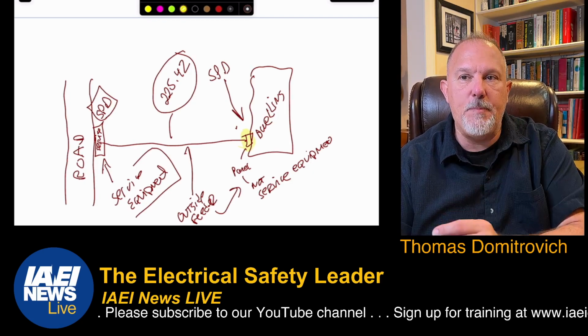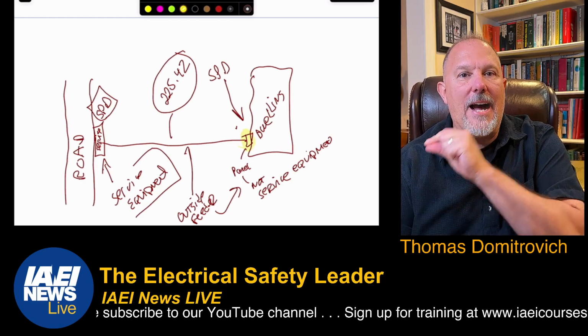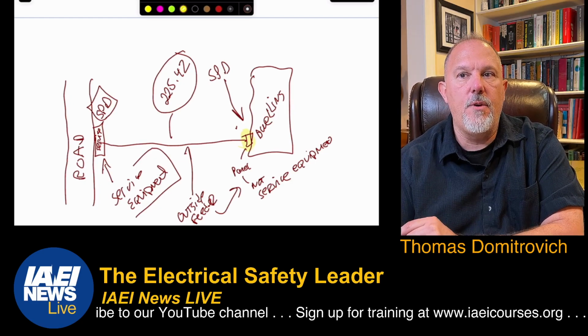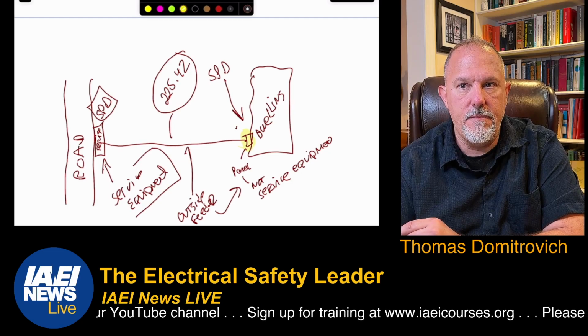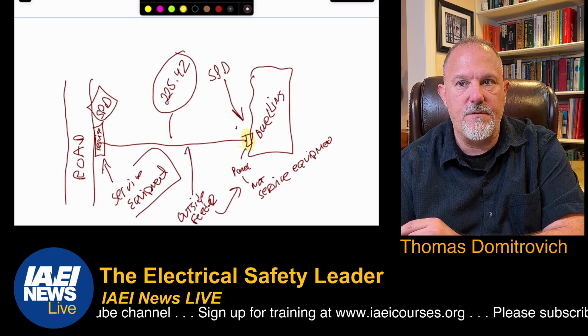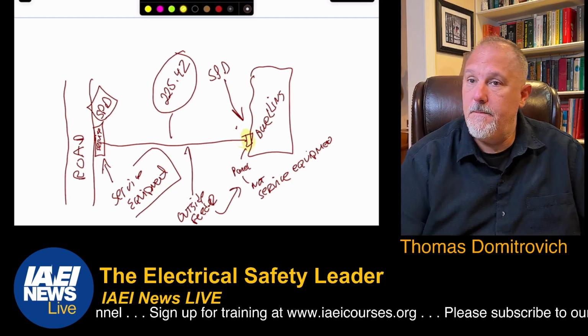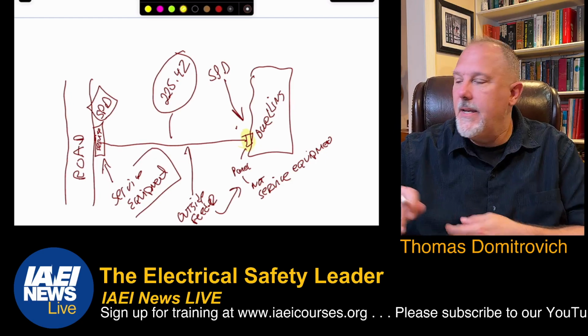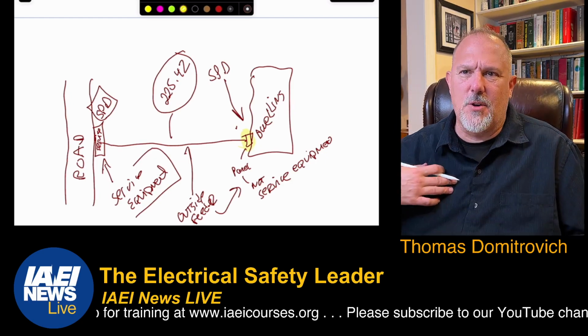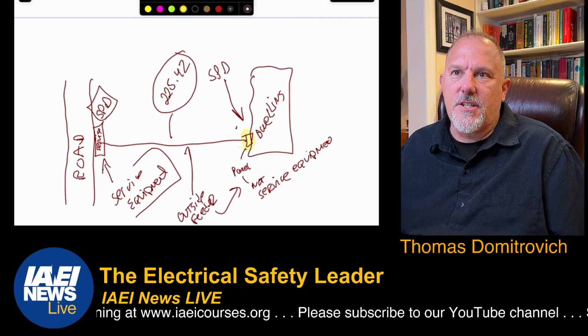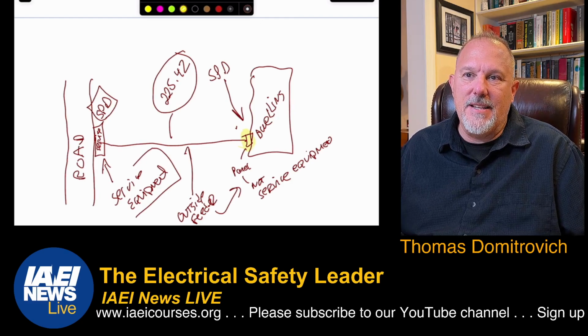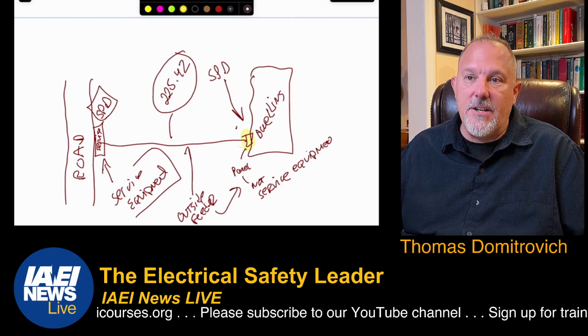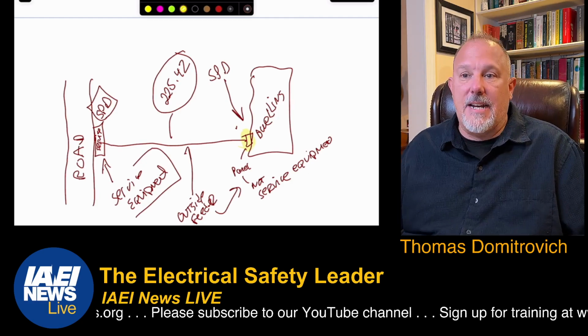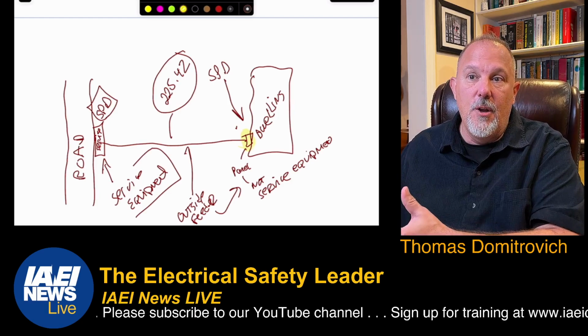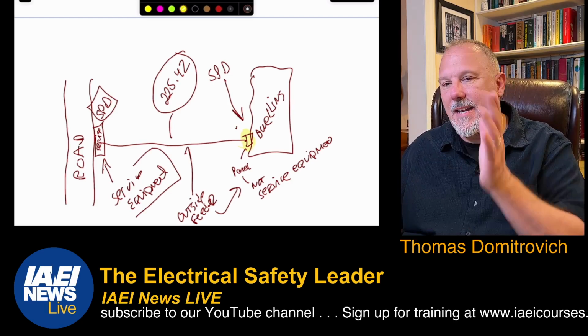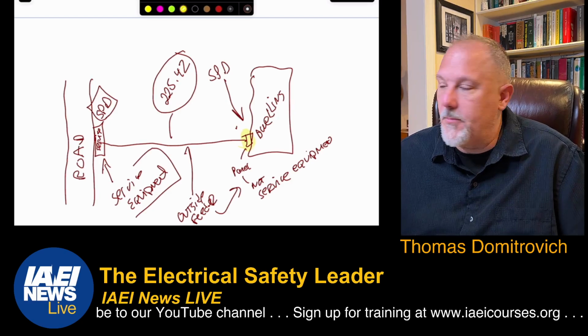If there's something special that just applies to outdoor feeders, then you would find it in 225, outside branch circuits and feeders. Now, different topic. In any case, you know where my head was going. What do I need 225 for? Why didn't I make just a part in 215 that said outside feeders, and then a part in 210 for outside branch circuits, if there's anything special for outside branch circuits and feeders? But in any case, different day, different public input.